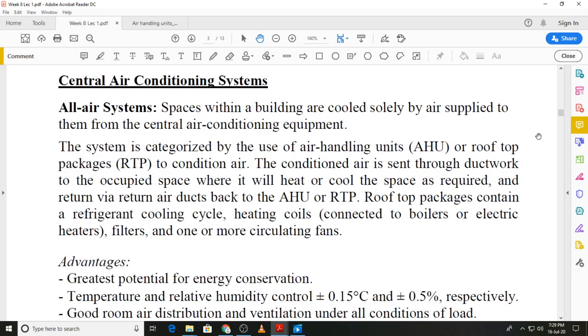We now move on to central air conditioning systems, and there are three broad categories: all-air systems, air-and-water systems, and all-water systems. We distinguish between them according to the mode of energy transfer. If energy transfer in the conditioned space is done solely through air, that is known as an all-air system. All-air systems use air handling units or rooftop packages. The difference is that in a rooftop package the refrigeration system is also present, whereas in an air handling unit the refrigeration system is separate and located in the plant room.